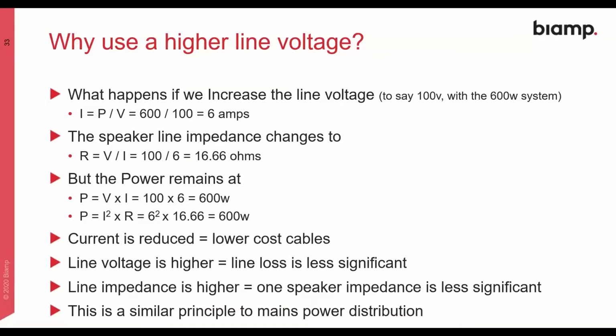So what happens if we increase the line voltage to, for example, 100 volts with this 600 watt system? So using I equals P over V, we get 6 amps. So it's a significant reduction in the current we've used there. The speaker line impedance would then change to be 16.6 ohms, but the power remains at 600 watts. So using P equals V times I, we get 100 times 6 equals 600 watts. Or using P equals I squared times R, we still get 600 watts.